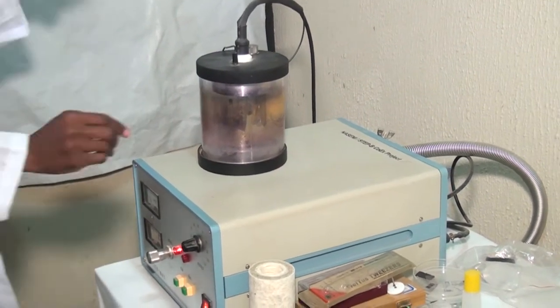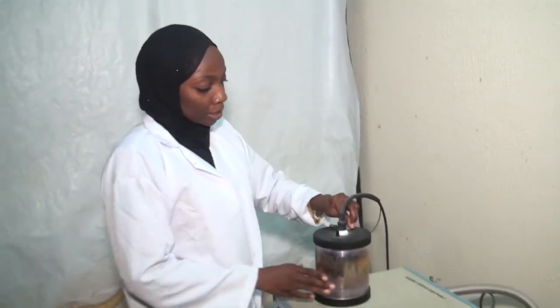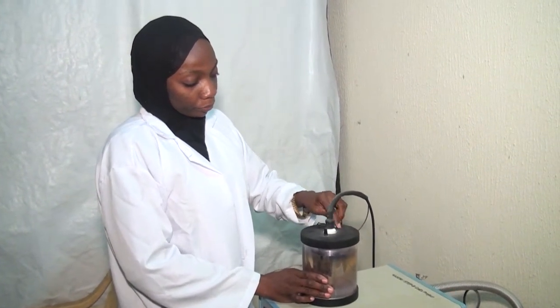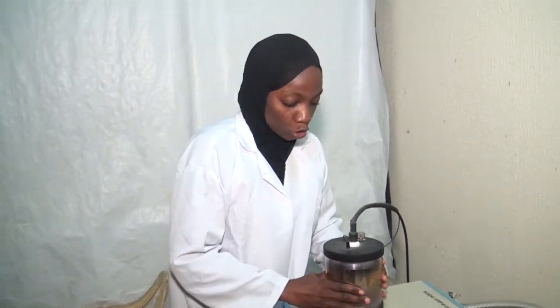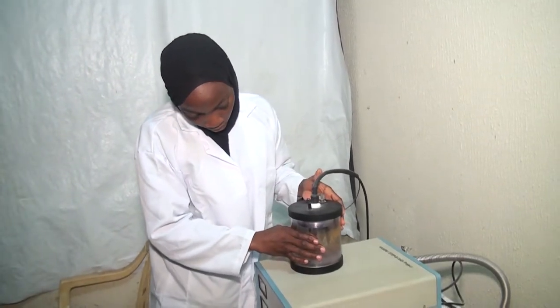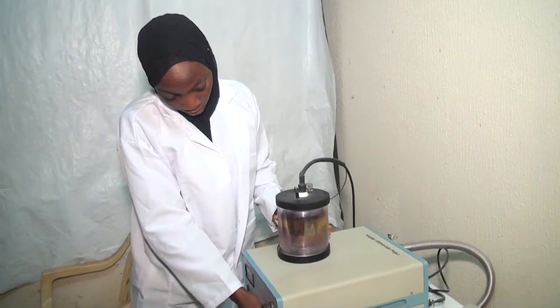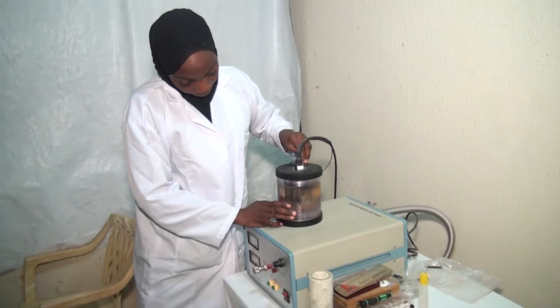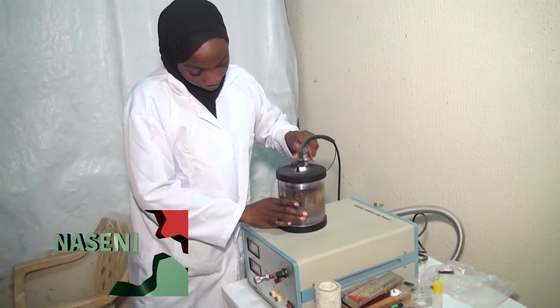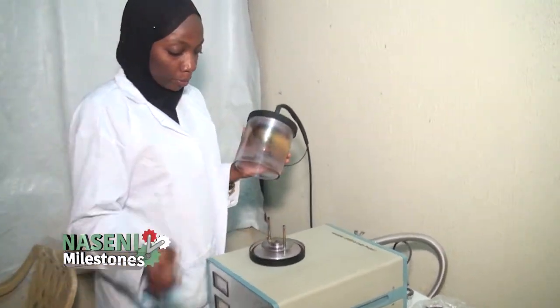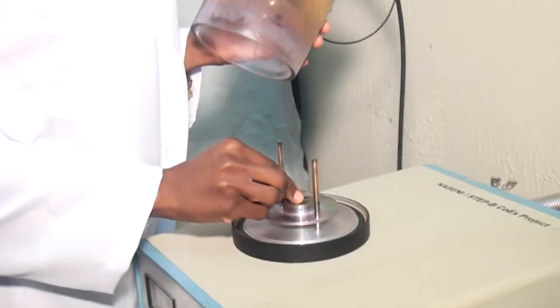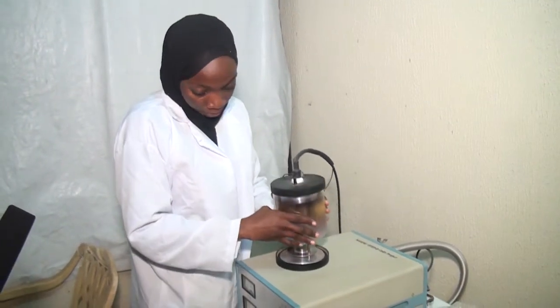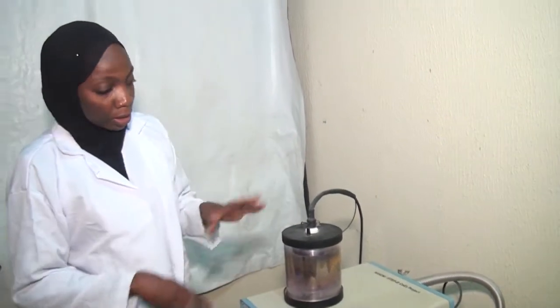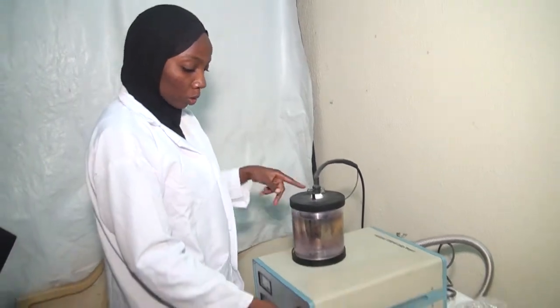So the first thing we do here is to switch on the machine, switch on the system, then you vent the system. After venting it, you wait for some minutes. Okay, then you open the sample chamber. This is our sample we intend to coat. Okay, there is yam flour on the sample slide. Then you put it here with a masking tape. Then you cover the sample chamber, which is in a vacuum, so it works under a vacuum condition.